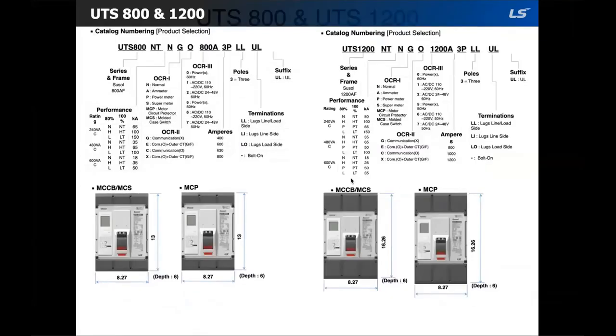And finally, your UTS 800 and 1200. So this is a little different. The UTS 800 has 6 performance ratings, but the UTS 1200 has 2 additional performance ratings: the 80% P rating and then the 100% PT rating. And then the UTS 800 and 1200 incorporate LS electronic OCR trip units. There are several options for OCR trip unit configuration. And as a result, the OCR has its own dedicated section.